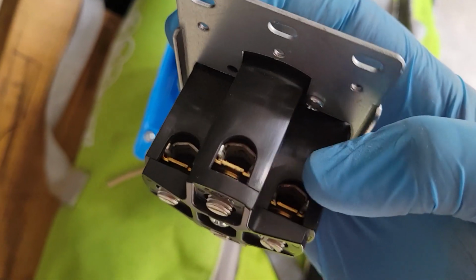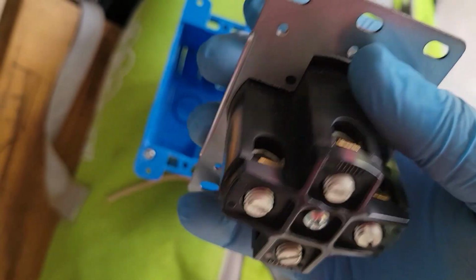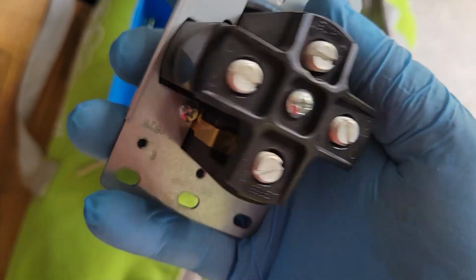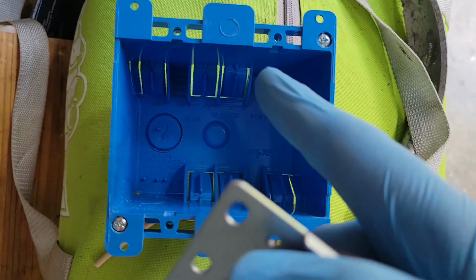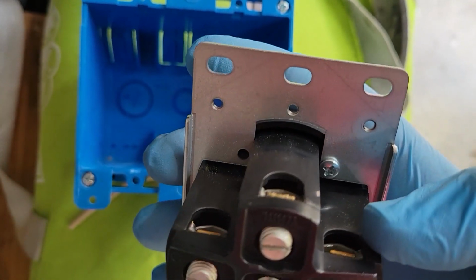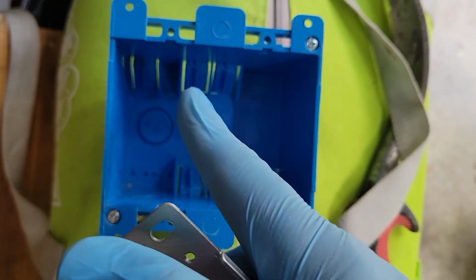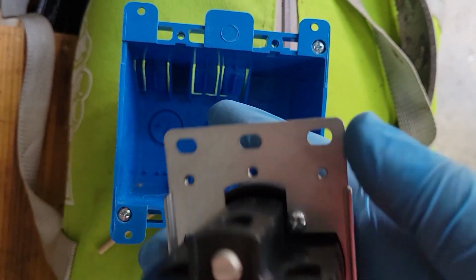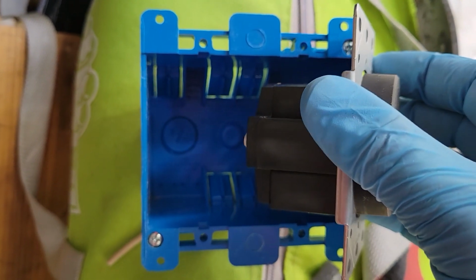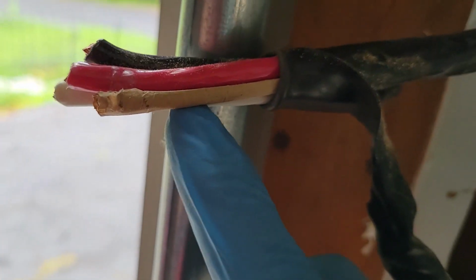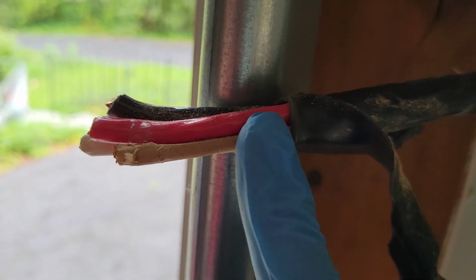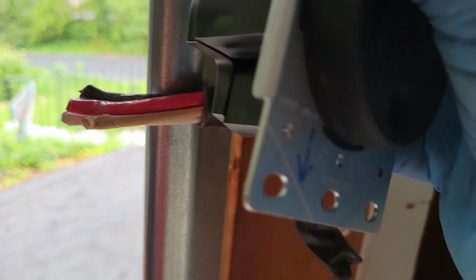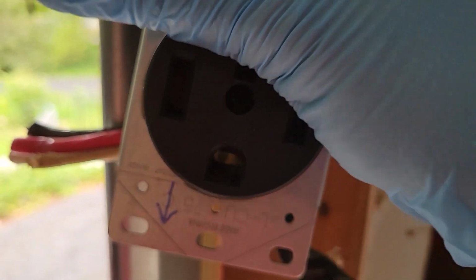Now the other challenge is on the back side, the clamps are facing up except for the ground, which is on the side. That means ground has to come in and go down to the bottom of the box, while the two hots and the neutral need to feed right off the top, and there isn't a lot of space in there to maneuver this 6-gauge cable. So a little pre-planning and knowing which way you're going to face the ground on your receptacle will pay off later.